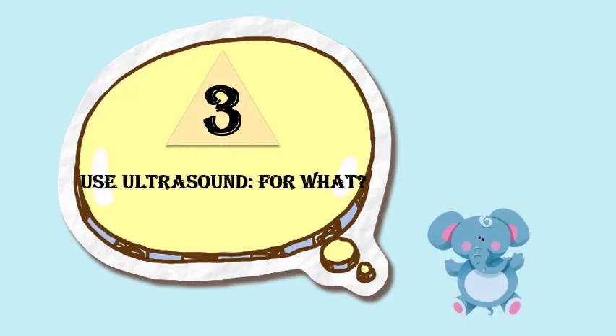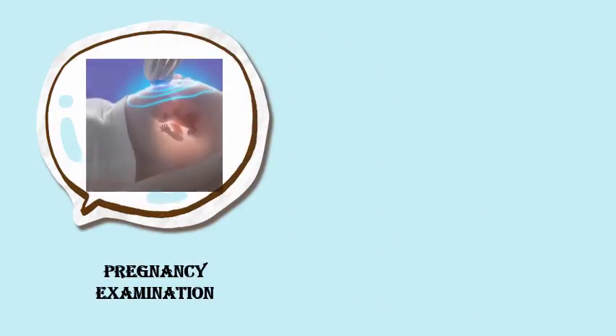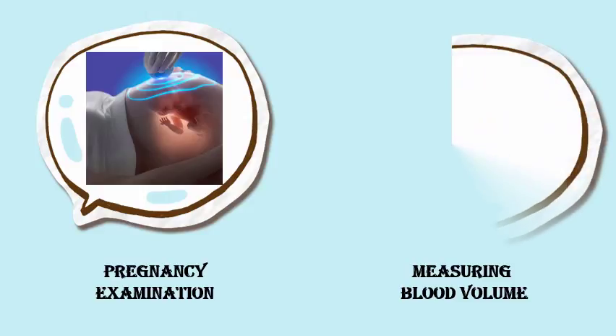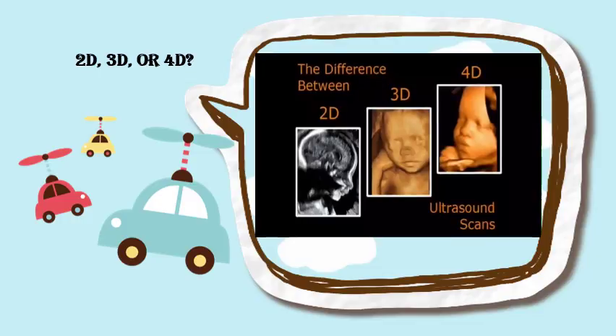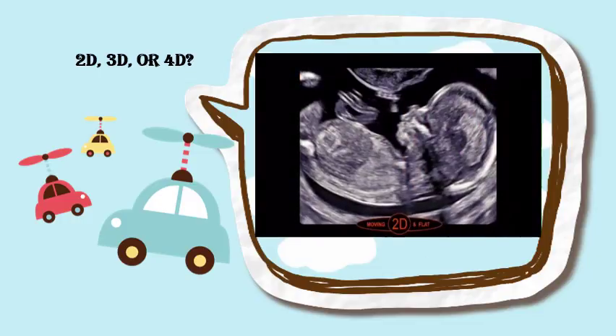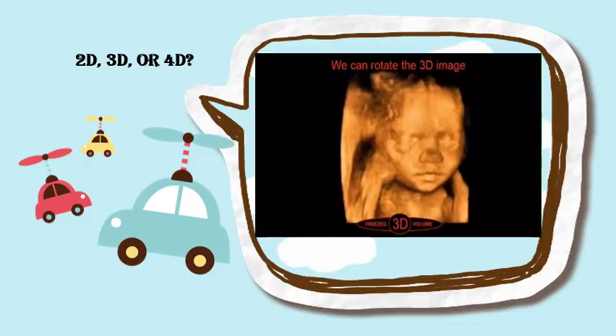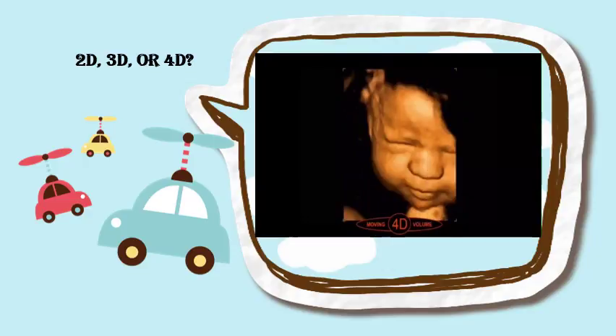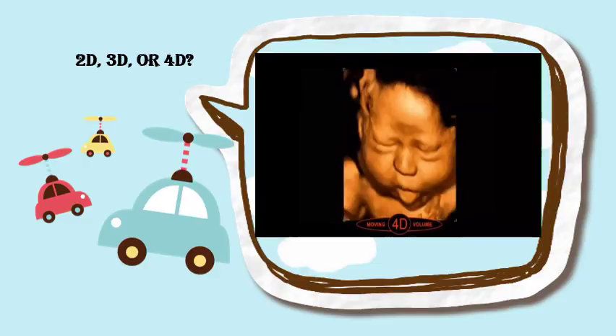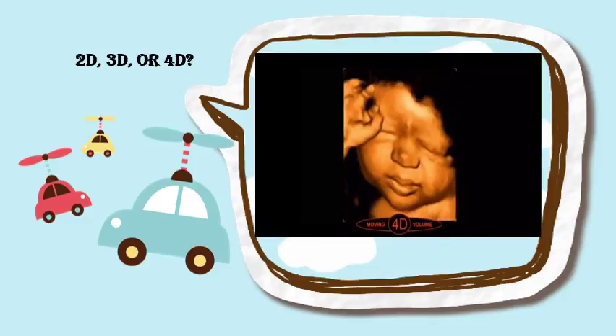4D scanning can provide more information about abnormalities and make a significant contribution to understanding organ anomalies. 4D ultrasound scanning can be applied in the cardiovascular system and pregnancy. Devices used in 4D ultrasound are almost the same as in 2D ultrasound: a probe with a piezoelectric transducer to produce ultrasound and receive echoes, and an ultrasonic scanner to form and display images.